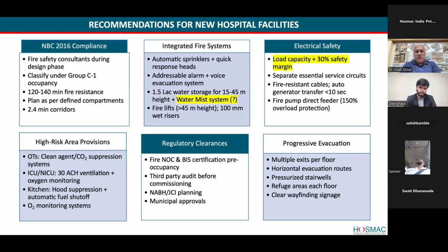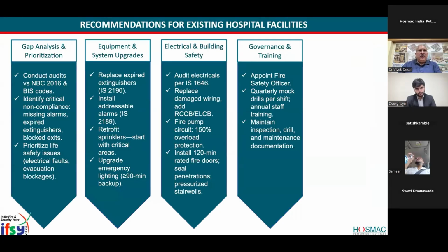All regulatory compliances should be in place: fire NOC, BIS certification, third party audits, municipal approval, yes or no. All right. Then, for existing hospital facilities, the gap analysis. Whatever we have learned today, we should do a gap analysis of where we are as compared to what is required, and then prioritize the life safety issues, mostly electrical short circuit areas. Please do check for any egress point blockages, all of that. Equipment system and upgrades wherever required: install addressable alarms, retrofit sprinklers wherever required, start with critical areas to begin with, and then slowly, because everything costs money.